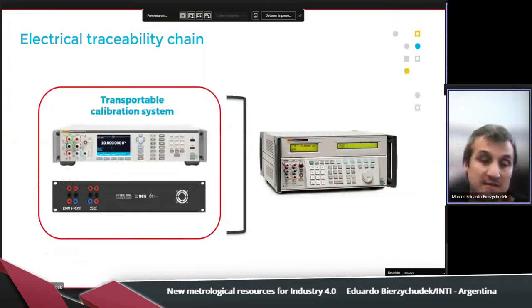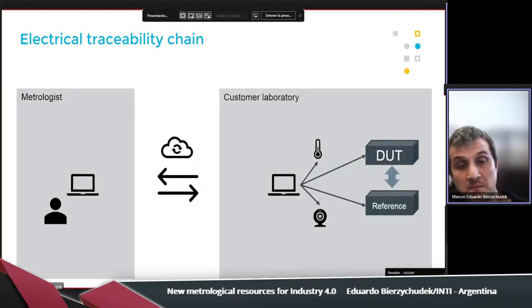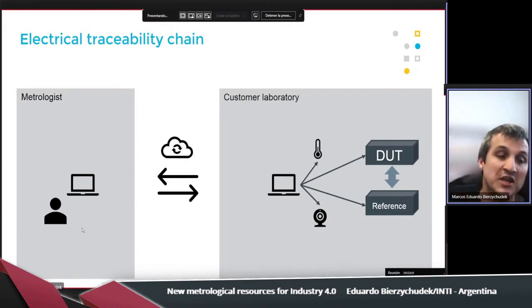Another advantage of the new system is that it is a transportable calibration system. It's completely impossible to move the actual system to a customer lab. It is a lot of instruments, but these two instruments are very simple to transport. I have to be clear that some resistors are included in the multiplexer box. So in a sense, we eliminated the LCR meter, we eliminated the AC voltmeter, which is a more expensive device, and we don't use all the resistors that are used nowadays. In this way, we can implement the remote calibration. This means carrying the standard directly to the customer's laboratory, and the metrologist can be in his lab working and controlling the measurement remotely by internet.